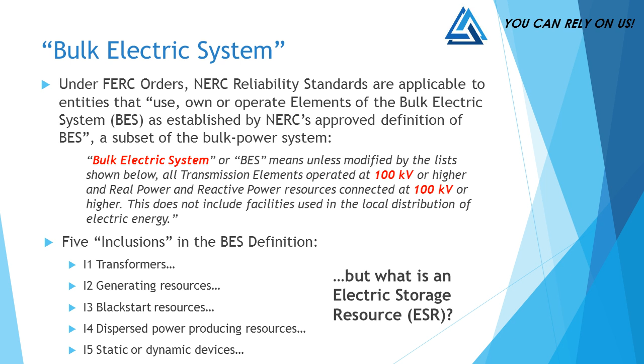I2 says: a generating resource, including the generator terminal through the high side of the step-up transformer, connected at a voltage of 100 kV - I want to highlight that, it's 100 kV here - with a gross individual nameplate rating greater than 20 MVA, or gross plant facility aggregate nameplate rating greater than 75 MVA.